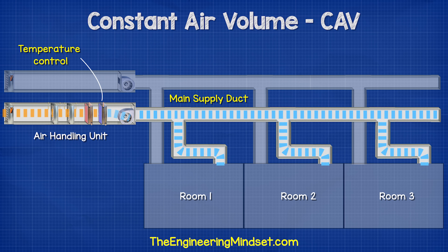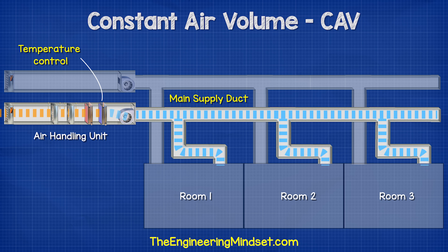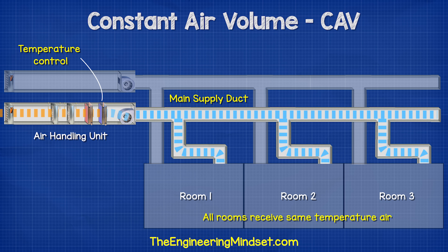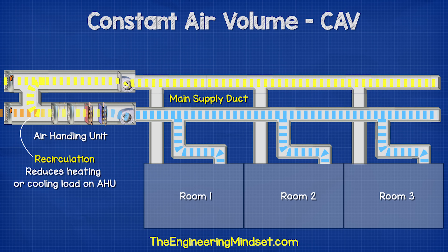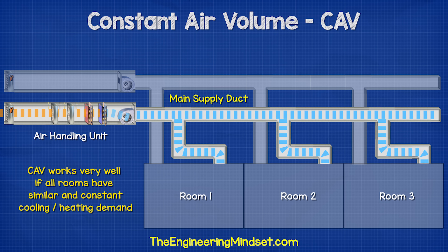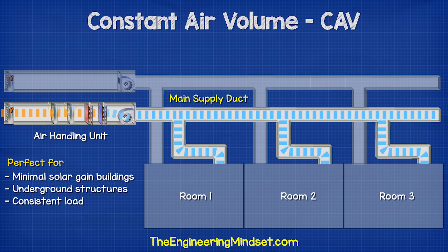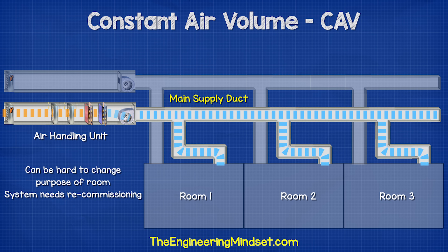From this schematic representation of the CAV system you can see how it's all connected. Notice that all of the rooms are connected to this main duct and the only form of temperature control is in the main AHU, meaning all rooms receive the same temperature air at a constant volume. Some AHUs have the ability to recirculate a portion of the air back into the supply stream to save energy, but this is not always used or permitted by local regulations. The CAV design would work very well if all of the rooms had a similar cooling demand — for example, if the building was underground or had minimal solar heat gains and each room had a consistent heat load that didn't vary too much.